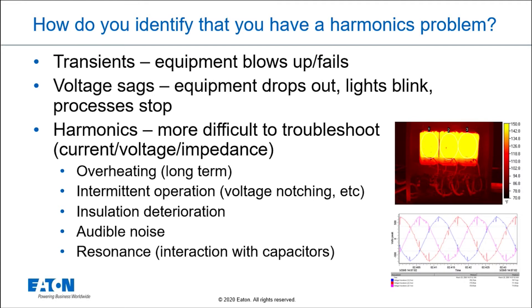Looking at the picture here, the transformer on the right is an infrared scan showing very high current distortion and very high heating. So if I have long-term overheating, I likely could have harmonics issues. If I have intermittent operation — things that don't work correctly, PLCs locking up — I could have a harmonics issue.